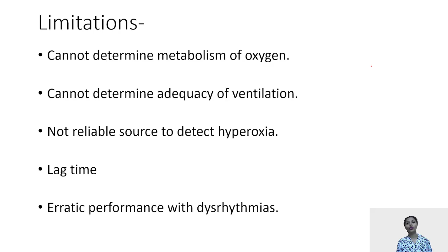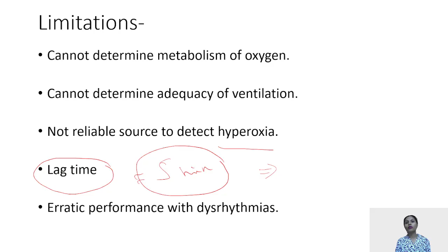Now, the pulse oximeter has its own limitations which you all have to remember. First, it cannot tell you anything about the metabolism of oxygen or the ventilation part. Second, it is not a reliable source to judge oxygen toxicity. Third, it has a lag time of at least 5 minutes. Lag time means that your partial pressure of oxygen is decreasing and still your saturation is coming correct. There is a lag time. And lastly, it has erratic performance when the pulse rate is irregular or you have dysrhythmias, then the pulse oximeter is not a very reliable source to measure the oxygenation.